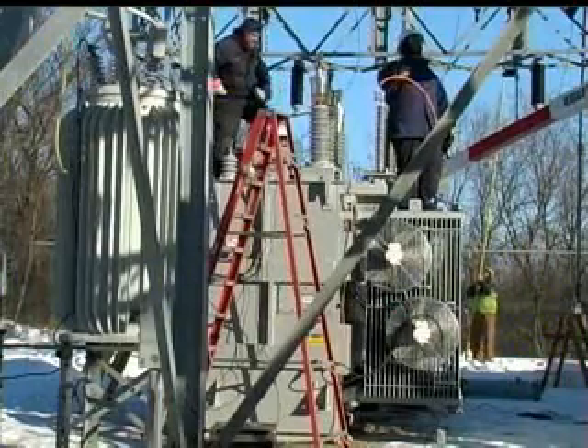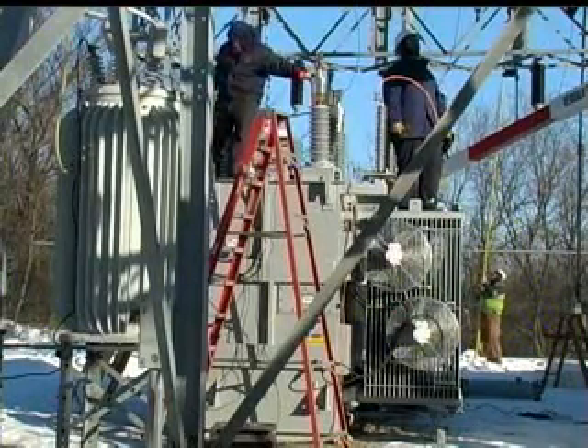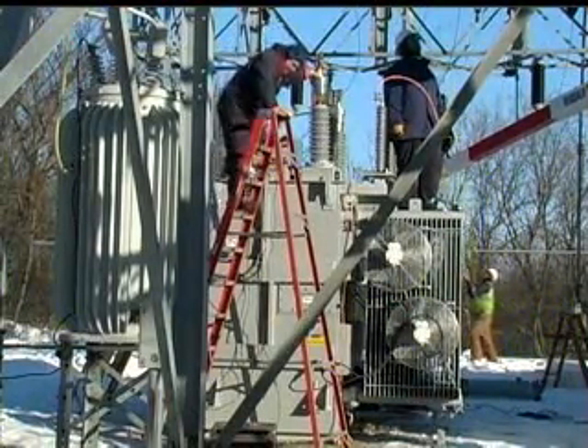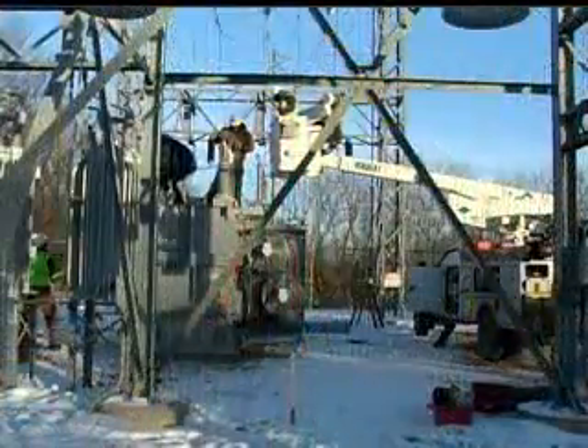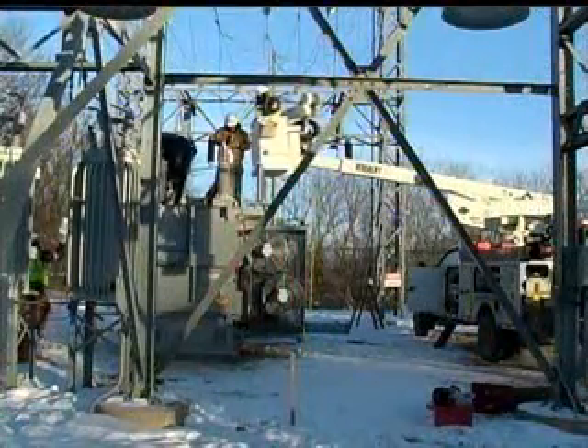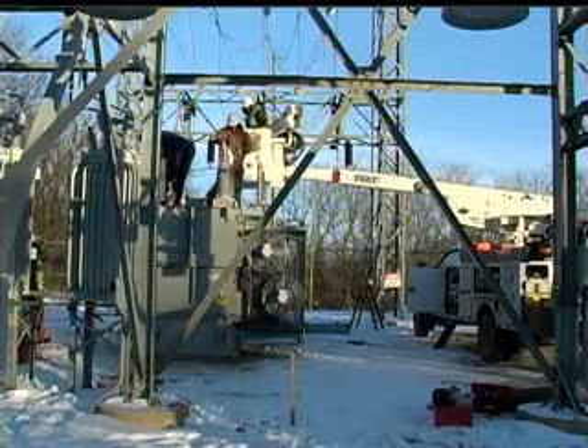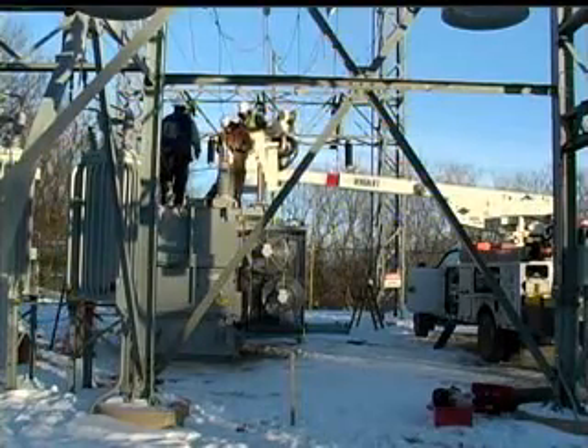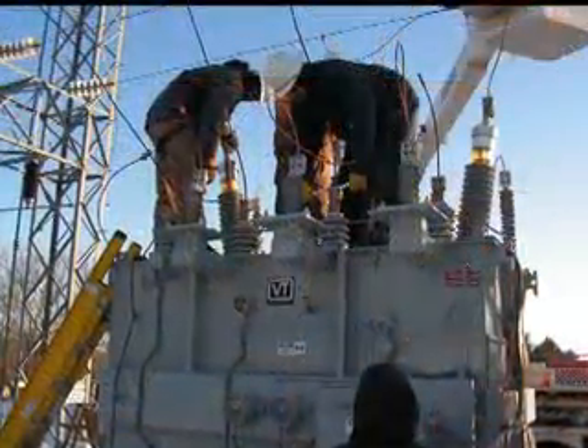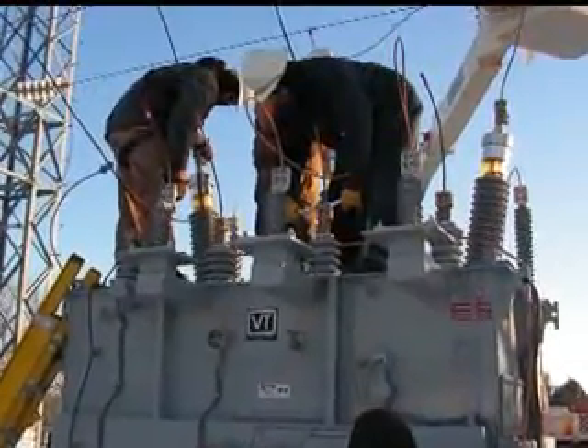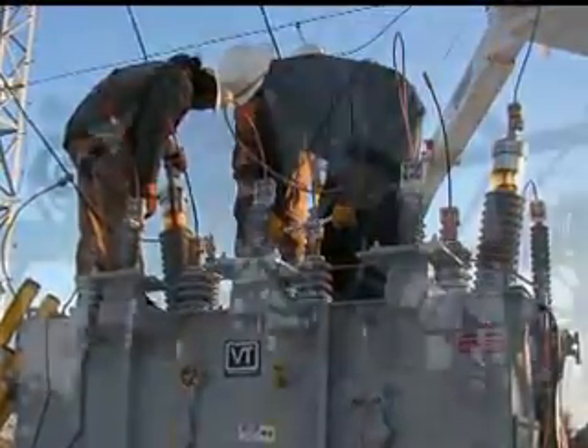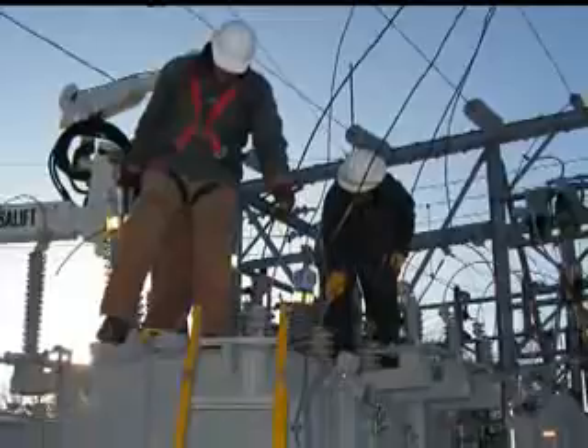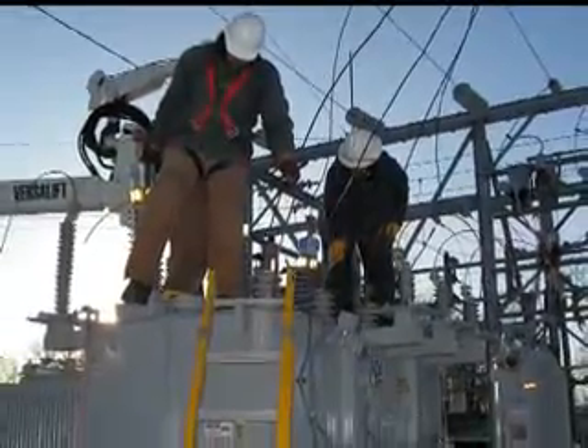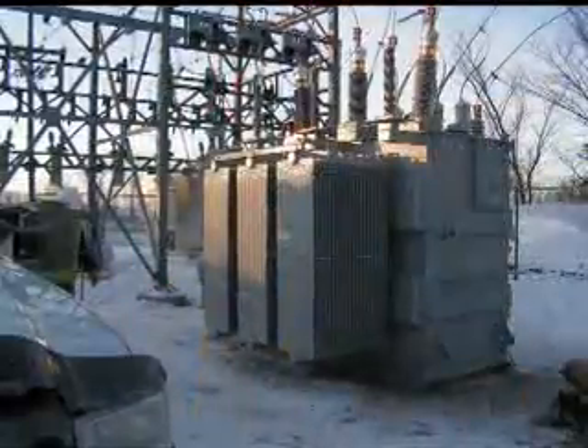After the bushings and lightning arresters are installed, a technician from Great River Energy performs metering tests. These ensure the transformer still meets factory specifications and that none of its settings have moved in transit from the factory. Also, Steele Waseca technicians can start hooking up the high and low voltage sides of the new transformer and ready the substation to go back online.